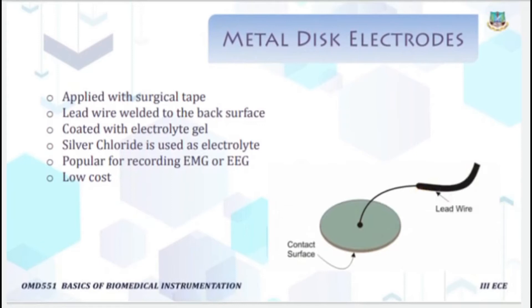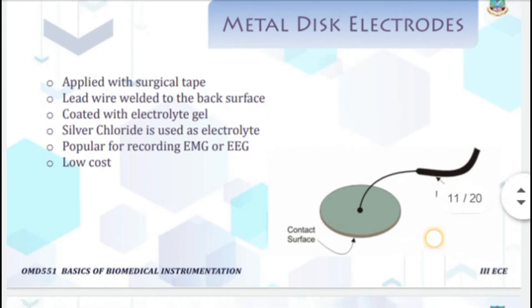The next type is the metal disc electrode, applied with a surgical tape. It is a circular plated electrode. The lead wire is connected to the back surface of the electrode, and it is also coated with electrolyte gel — normally silver chloride is used as the electrolyte. It is popular for recording EMG or EEG and the cost is very low compared to others.